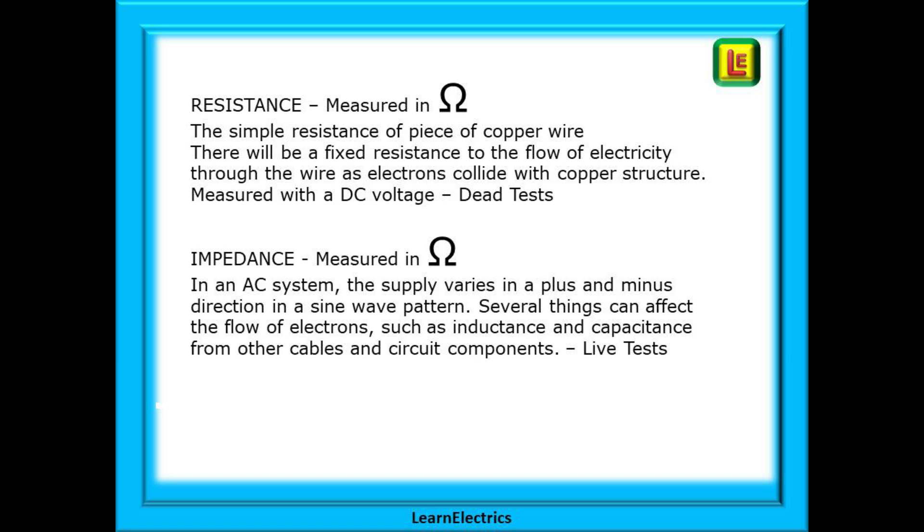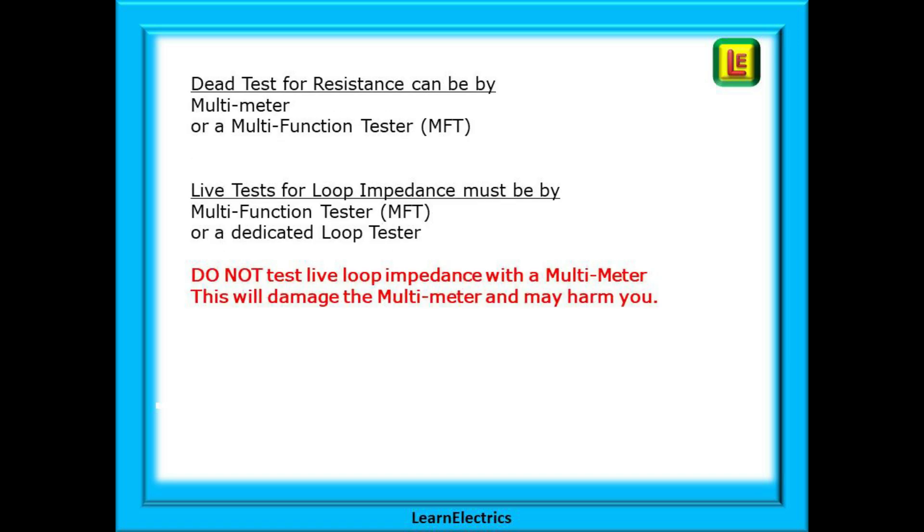With most installations of 50 cycles per second resistance and impedance are almost the same value. A dead test for resistance can be by multimeter or a multi-function tester MFT, but live tests for loop impedance must be by multi-function tester MFT or a dedicated loop tester. Do not test live loop impedance with a multimeter. This will damage the multimeter and may harm you.